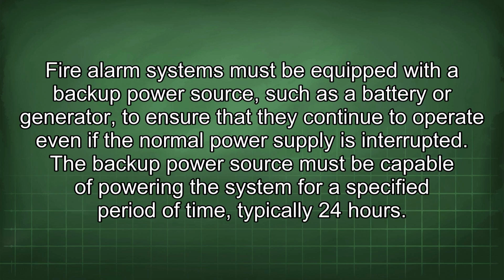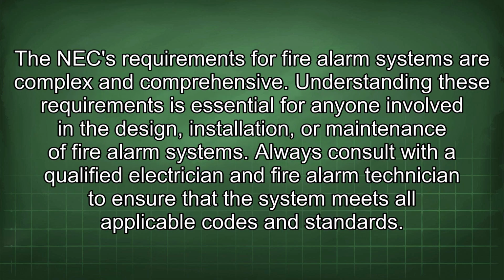Fire alarm systems must be equipped with a backup power source, such as a battery or generator, to ensure that they continue to operate even if the normal power supply is interrupted. The backup power source must be capable of powering the system for a specified period of time, typically 24 hours. The NEC requirements for fire alarm systems are complex and comprehensive. Understanding these requirements is essential for anyone involved in the design, installation, or maintenance of fire alarm systems.